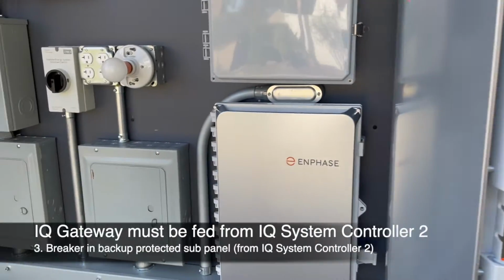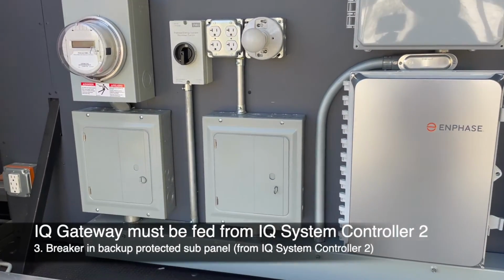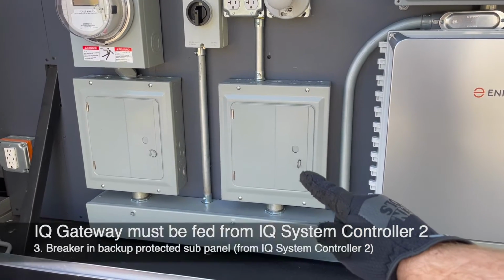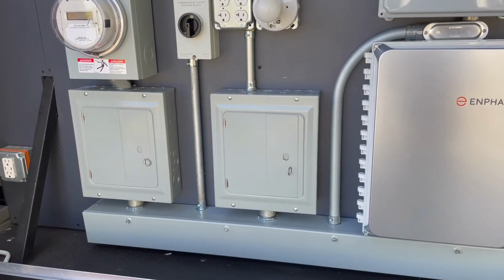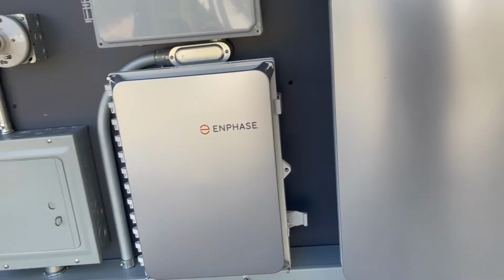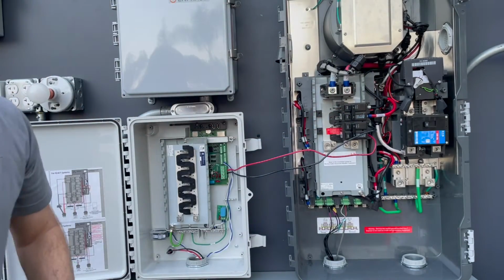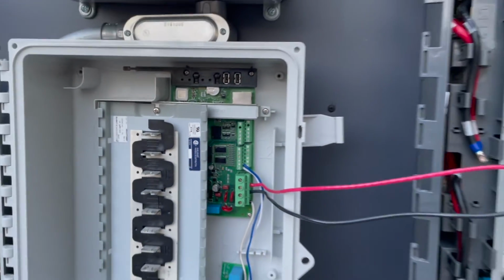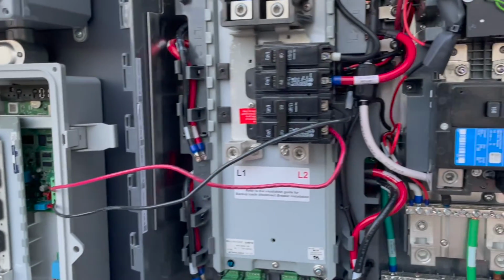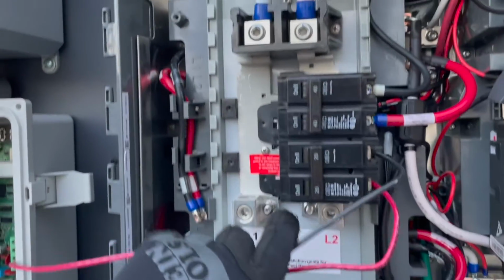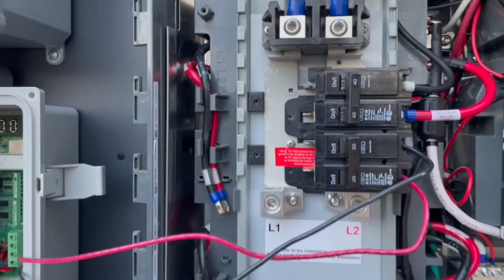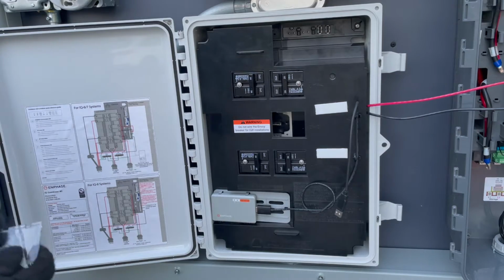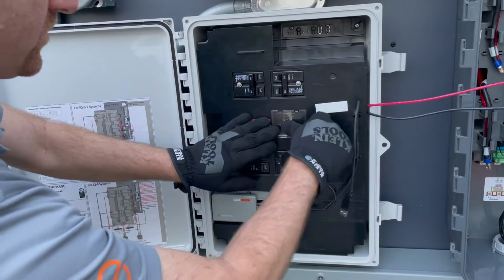A third option is to place the IQ Gateway breaker in the backup protected subpanel. Just be sure it's not connected to a contactor or any load control device. Here's a quick visualization of the wiring path from the IQ Gateway to the lower right breaker location. You'll safely install this in a raceway, of course, and you'll cover the unused breaker location with a protective filler plate.